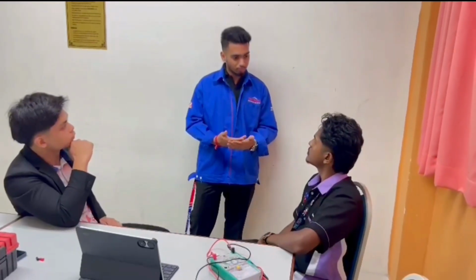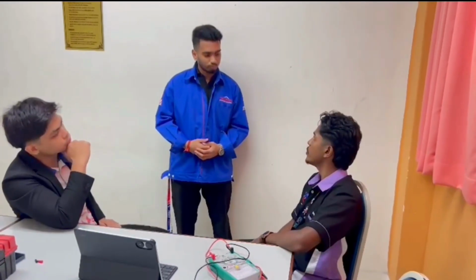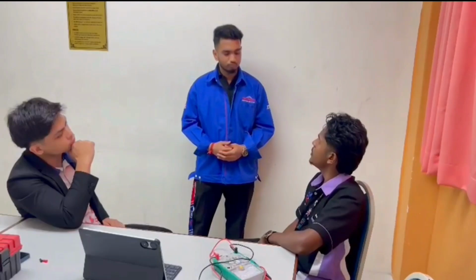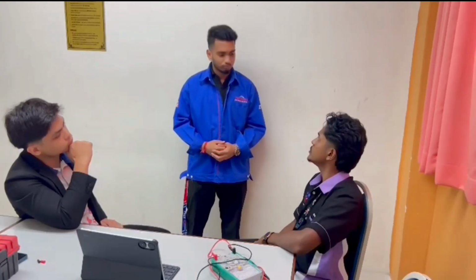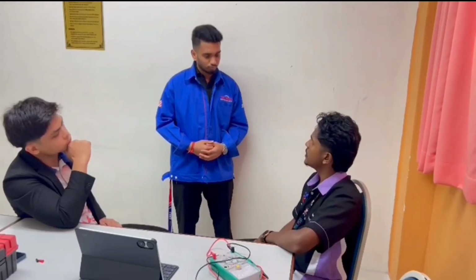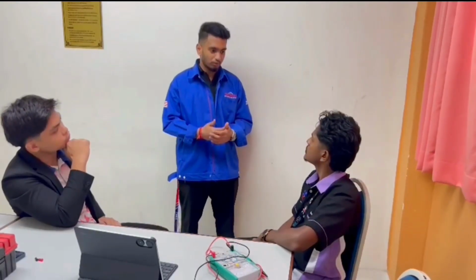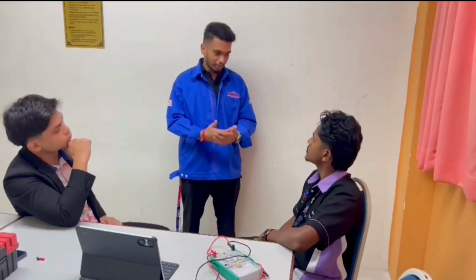Is there anything we can do to prevent this from happening again? Yes, we should make sure the monitor follows its scheduled calibration and maintenance checks. The staff should also report irregularities immediately instead of continuing to use the equipment. And make sure the maintenance record is updated after the monitor is repaired.